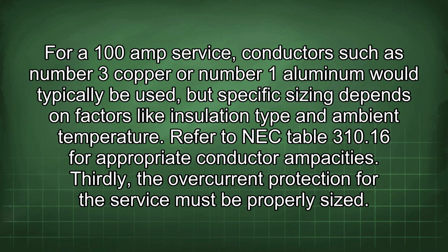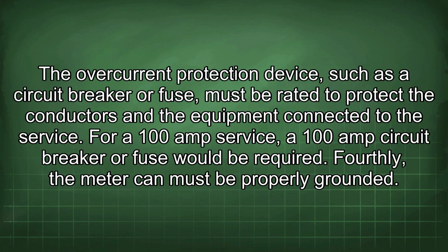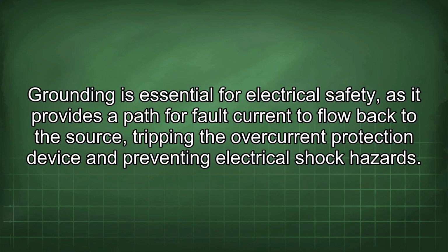Thirdly, the overcurrent protection for the service must be properly sized. The overcurrent protection device, such as a circuit breaker or fuse, must be rated to protect the conductors and the equipment connected to the service. For a 100 amp service, a 100 amp circuit breaker or fuse would be required. Fourthly, the meter can must be properly grounded. Grounding is essential for electrical safety as it provides a path for fault current to flow back to the source, tripping the overcurrent protection device and preventing electrical shock hazards.